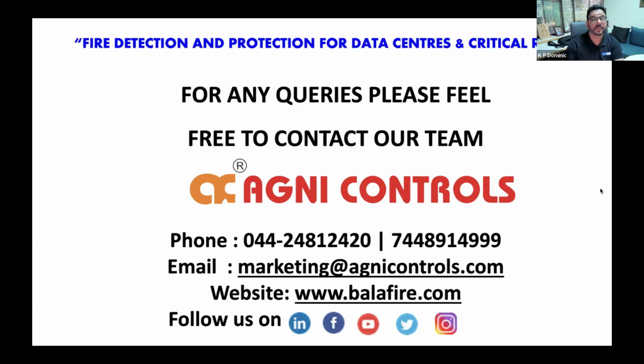Kapileshwar asks what type of detector for fire suppression should be used inside a server rack panel, which has a maximum chance of generating an early fire. Arun, do you want to answer that? Yes. If it is a server rack or cabinet type of fire protection, there are two ways of addressing that. One is a low-cost version. For the low-cost version, you can go for our detect and extinguish system, which is a tube-based protection system. It is a low-cost one, and the extinguishing agent can be an FK chemical agent.